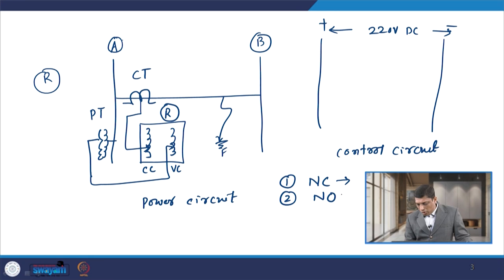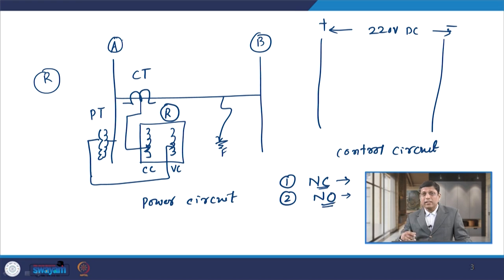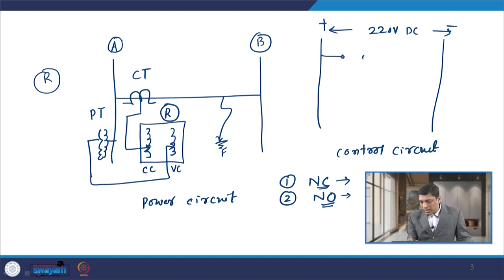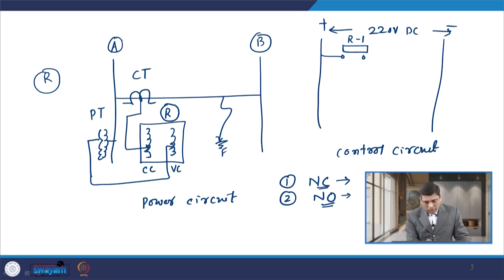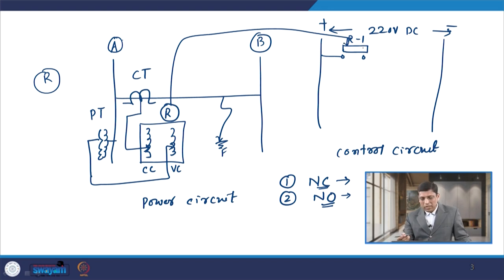A normally closed contact remains closed when the relay coil is de-energized, whereas a normally open contact remains open when the relay coil is de-energized. If we consider relay R with a normally open contact, that contact is called R1. Whenever any fault occurs on the line, the coil of the relay is energized and it gives signal to contact R1. Since this contact is normally open, whenever the relay coil is energized, this contact closes and gives further signal to the auxiliary relay.